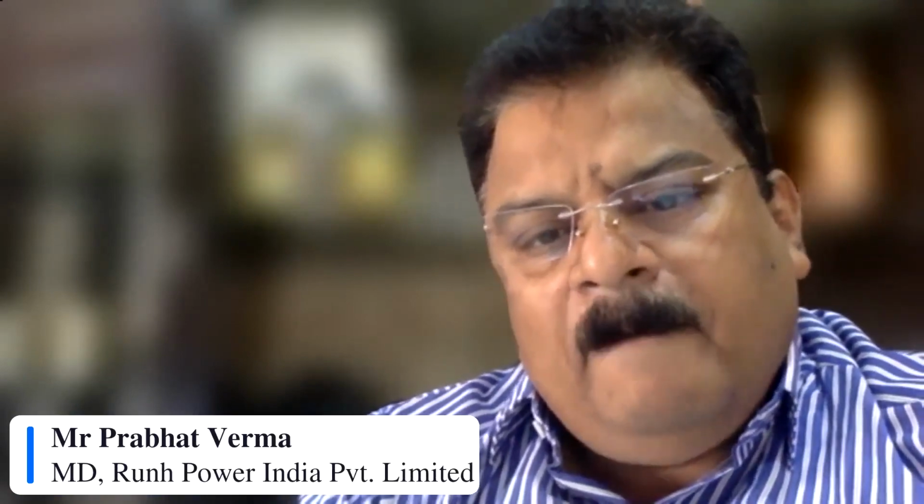So can you do the heat rate audit? I mean, can you visit a power plant and tell the developers what is the real heat rate and the variation online? Yeah, definitely. That's what we do. How many days does it take? See, it depends on whether they have the thermal performance curves available or not. If they don't have them, you have to use a simulation tool to generate those curves first. That's a big task. If they have performance curves, we can easily implement it.